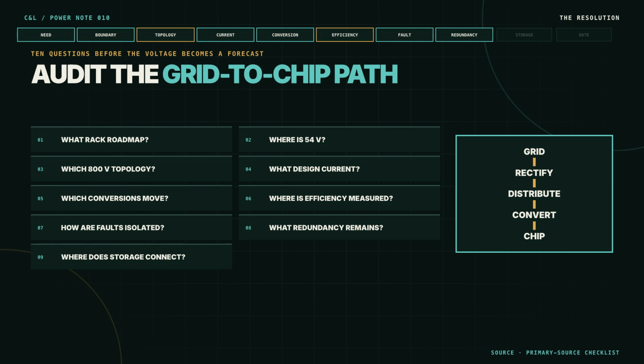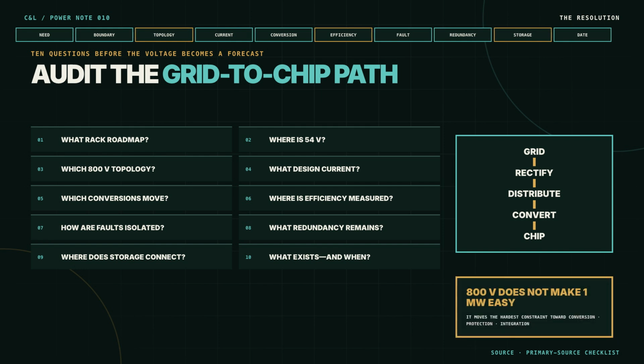800 volts does not make 1 megawatt easy. It moves the hardest constraint from raw current toward conversion, protection, and system integration. The winning design must prove the complete path from grid to chip.